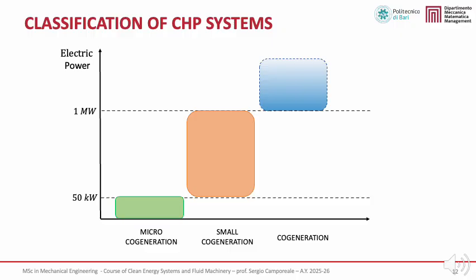Moving to higher power levels, we have small cogeneration systems, with electrical output ranging approximately from 50 kilowatts up to about 1 megawatt. These systems are commonly applied in hotels, hospitals, small industries, and commercial buildings, where heat and power demands are more significant and relatively continuous. Finally, above 1 megawatt of electrical power, we refer to large cogeneration systems. These plants are typically installed in industrial sites, district heating networks, or large energy facilities, where both thermal and electrical demands are very high. This classification is useful for selecting the most appropriate CHP technology according to the scale and application.